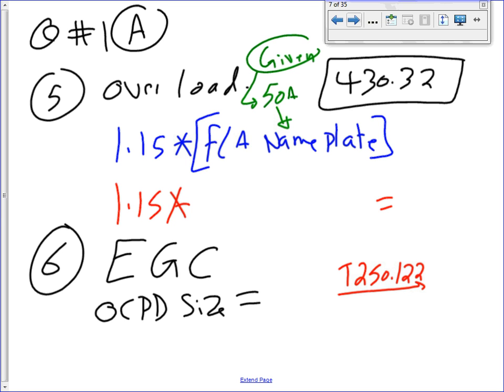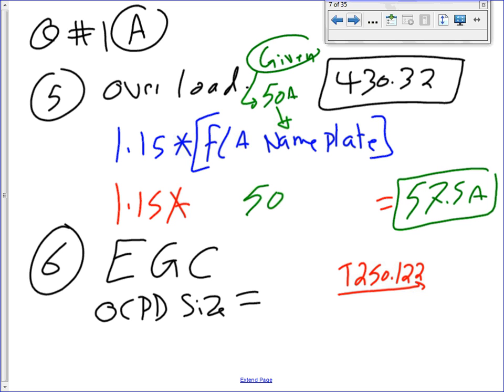Okay, so when you know the overload, you have no idea what the temperature rise or what the service factor are. Did they tell you anything about service factor? Could be anything. What's your default if you don't know? 115. So you're going to go to 115, guys. Take the 50, 115, and you've got yourself 57.5 amp and done.